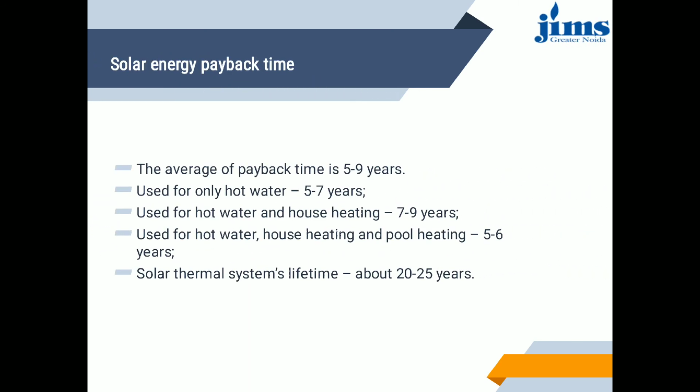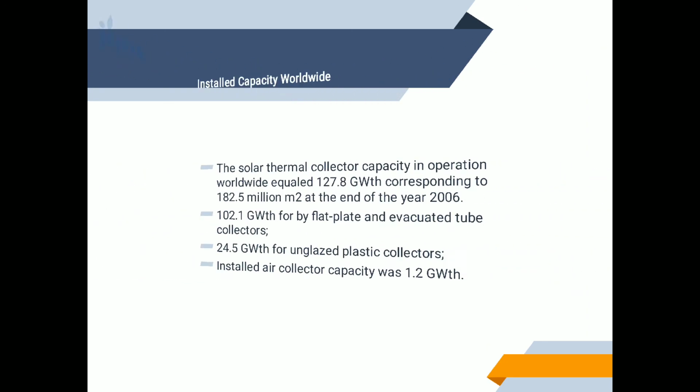Now solar energy payback time. The average payback time is about 5 to 9 years. Used for only hot water, it is 5 to 7 years, and used for hot water and house heating, it is 7 to 9 years. Used for hot water, house heating and pool heating, it is 5 to 6 years, and the solar thermal system lifetime is about 20 to 25 years.